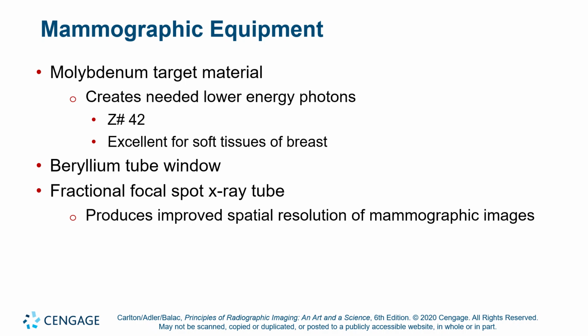Mostly it's just soft tissue. So we don't need as much penetration power, so we use reduced kVp in particular. And that's why we can get away with a different target material. Okay. We don't need 100 kVp, we only need about 20 to 25 to penetrate through a breast on average. The beryllium window is going to allow more of those low energy photons like we use in breast imaging to actually get through. It's not going to filter them out as efficiently as Pyrex glass or any sheet metal housing would. Okay, not housing, envelope. Two different terms.